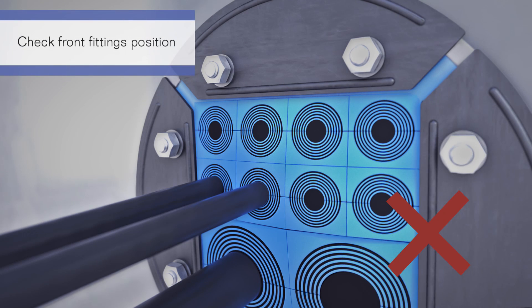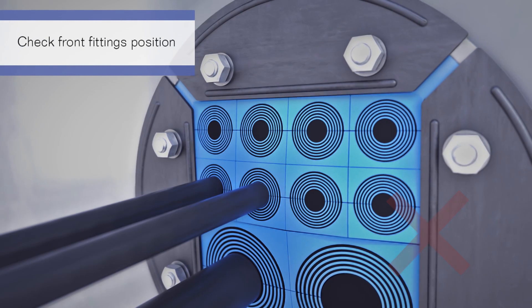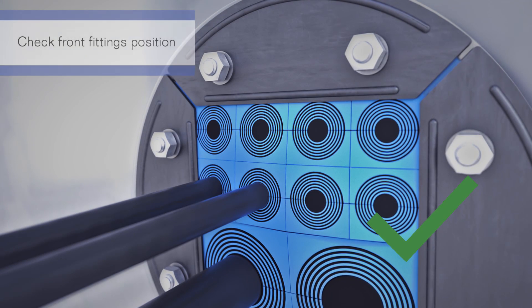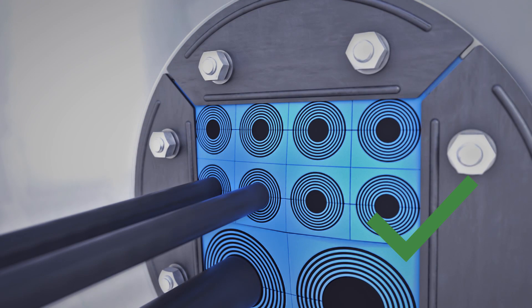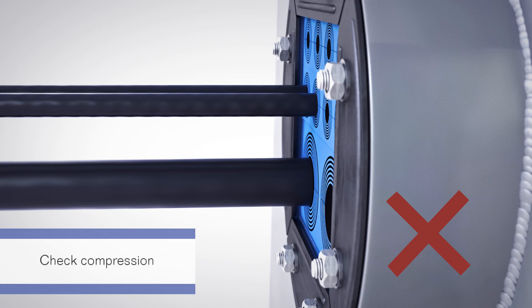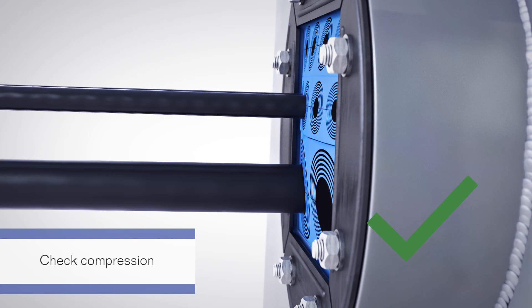Make sure the front fittings are pushed back to create a stop flange, securing modules after compression as well. If you use an R-frame, check the compression by verifying that the modules start to show convexity.